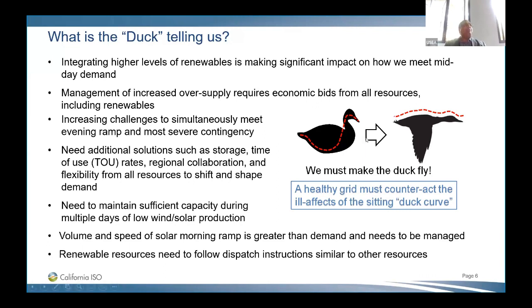It's important to maintain sufficient capacity during periods or consecutive days with very low wind and solar production. When policymakers look at the ability to serve 108% of energy needs plus export with non-carbon resources, the first thought is that we could get rid of the gas fleet. But no, you cannot. One of the biggest challenges is during sunrise: for six months of the year the load is pretty flat, and you get anywhere from 5,000 to 8,000 megawatts of solar coming onto the grid. You tend to see oversupply, high frequency, high area control error. How do you control that?